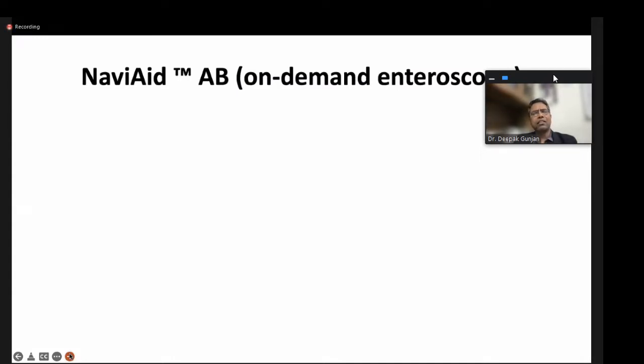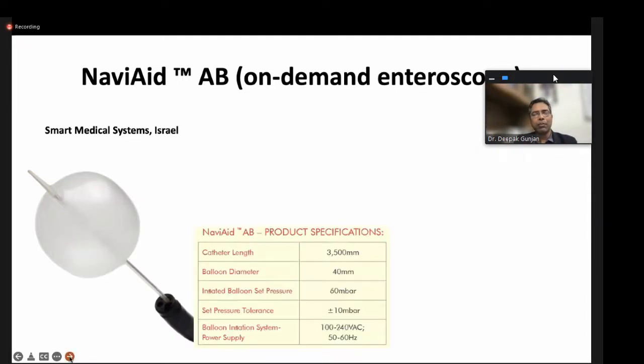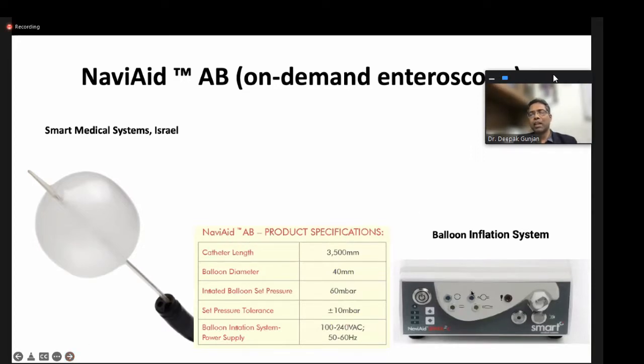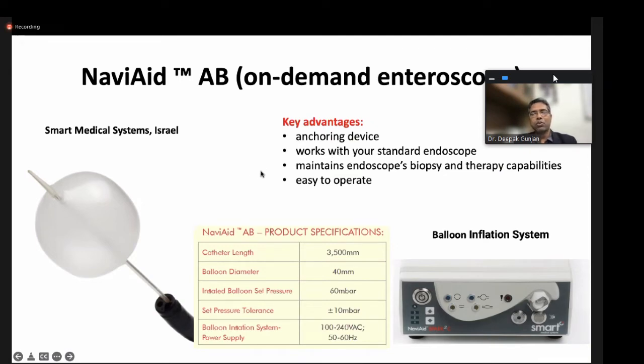The NaviAid, also called the on-demand enteroscope, was developed in Israel. It is a through-the-scope balloon that can be passed if the working channel is 3.7 or 3.8 mm. You can inflate the balloon and use it as an anchoring device to advance the endoscope. It can be used to complete a colonoscopy when advancement is difficult, or to go deep via retrograde or antegrade methods. After removing the balloon, you regain full therapeutic capability. However, there is limited worldwide experience with this device.